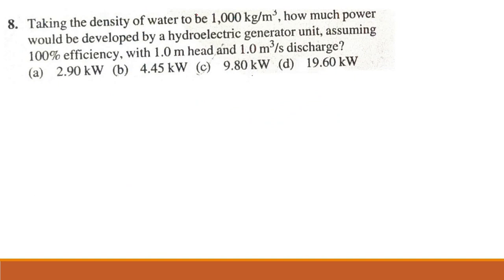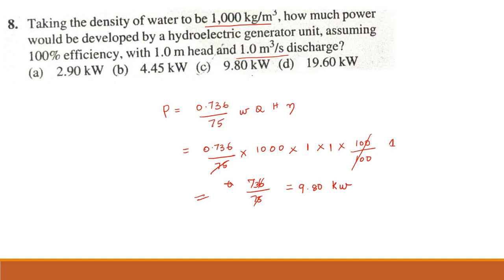Problem 8. Taking the density of water to be 1000 kg/m³, how much power would be developed by the hydroelectric generator unit, assuming 100% efficiency with 1 meter head and 1 m³/s discharge? The formula is P = 0.736/75 × W × Q × H × eta. So 0.736/75, density of water is 1000 kg/m³, discharge is 1, head is 1, eta is 100/100 which is 1. Multiplying 0.736 with 1000 gives 736 divided by 75, the answer is 9.80 kilowatts. Option C is correct.